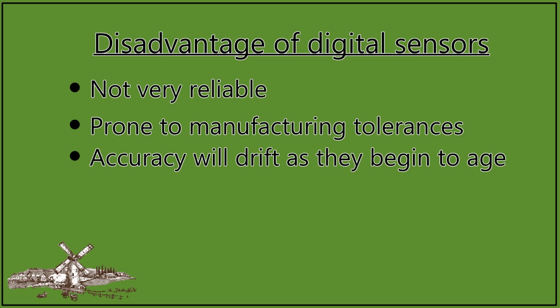So you may find that a temperature sensor may be accurate today, and in 2 months' time, it would be wildly off, and it could potentially be measuring a temperature 2 degrees higher than what it used to when we bought it brand new. So in order to account for the manufacturing error and the age, we have to come back to our controller every time we hatch, and we are going to have to determine whether our temperature and our humidity measurement is still reliable. And if the accuracy or the reliability of those sensors has changed and it is no longer reliable, we need to assist the controller into adjusting the temperature and the humidity measurements either up or down in order for them to give us an accurate, reliable measurement once again.